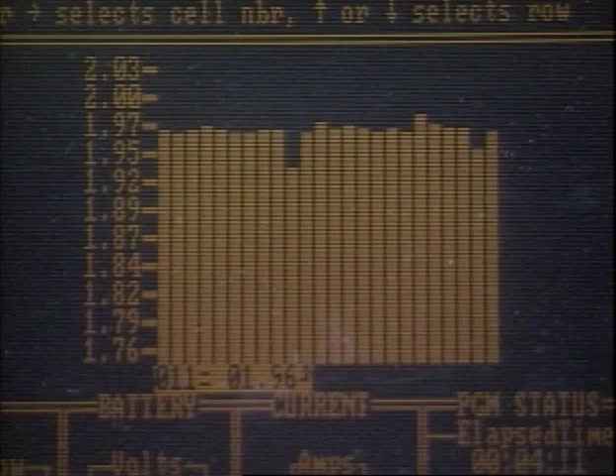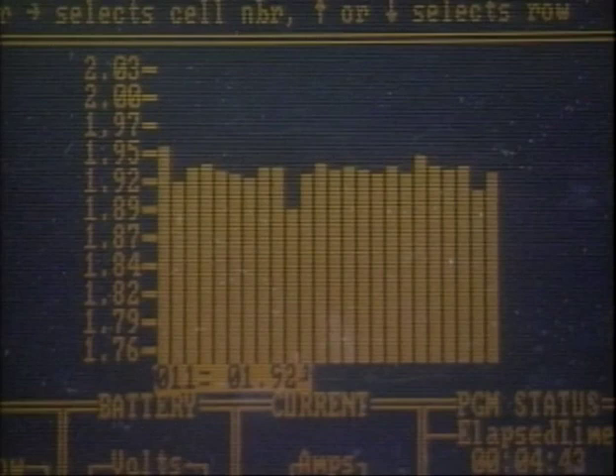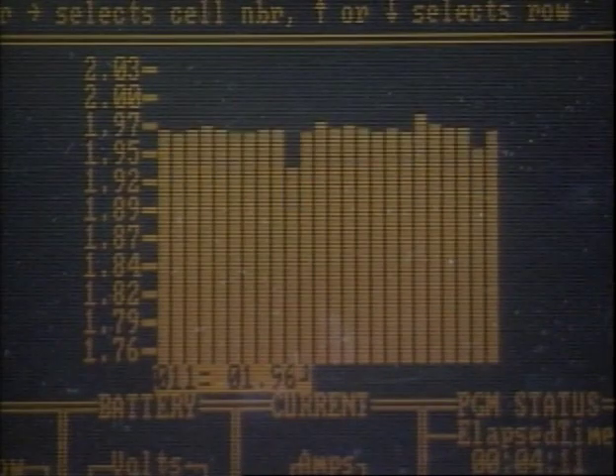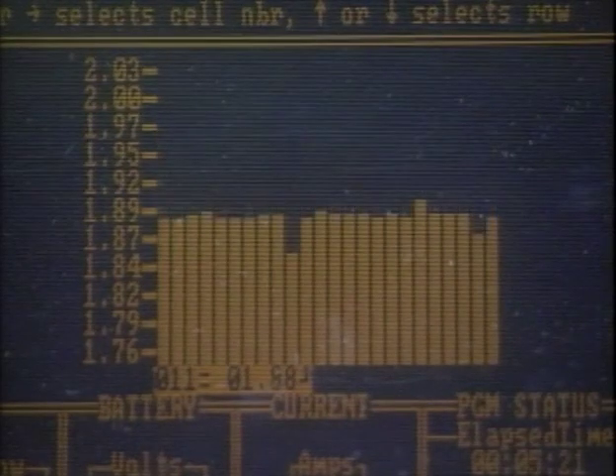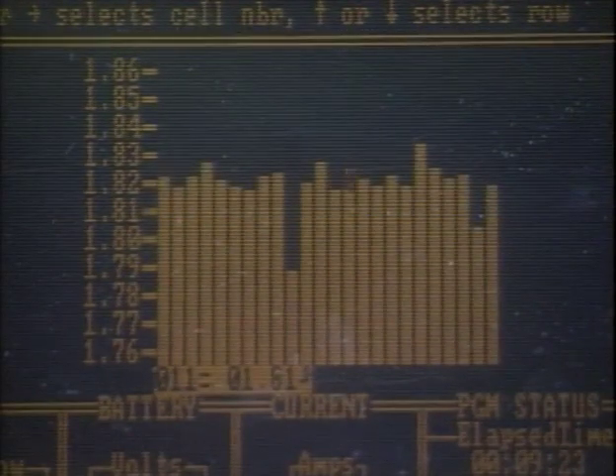During an integrity and capacity test, cell voltages typically change in a somewhat predictable pattern. At the start of the integrity test, cell voltages will drop sharply when the load is applied. Then, when the load is reduced for the capacity test, the voltages will recover to a higher level and hold steady for about a third of the total test time. Then the cell voltages will drop steadily through the rest of the test. For the last 20% of the test time, the voltages start to drop faster.